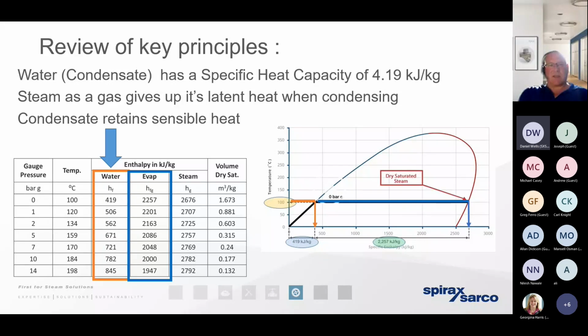And if you look at the bottom axis on the graph, it demonstrates that as the steam gets wetter, it's got less energy contained within it. So it's a double whammy. Everything we do with regards to good practice in steam systems should be with the intention of keeping the steam as dry as we possibly can. So there are other fundamentals we need to give thought to whenever we're looking at steam generation.